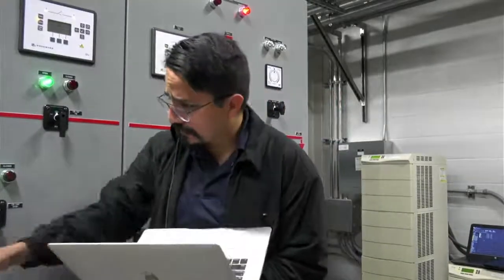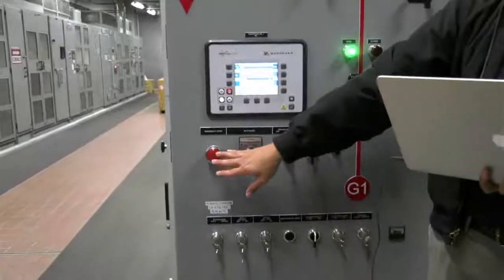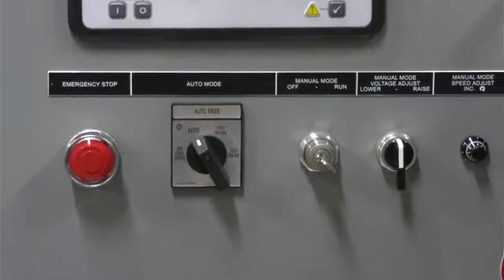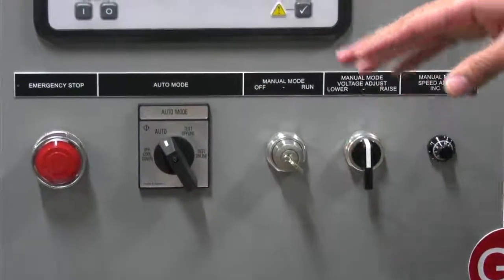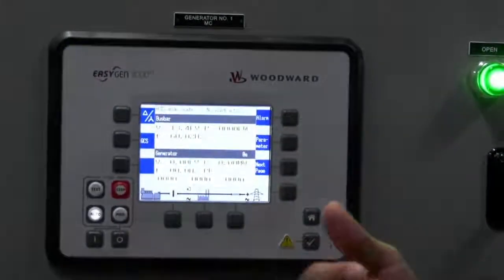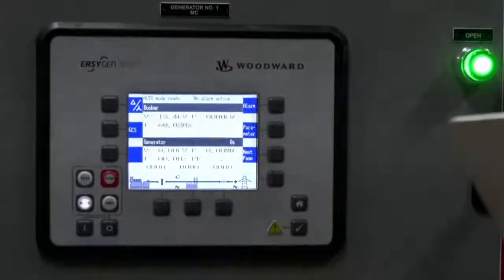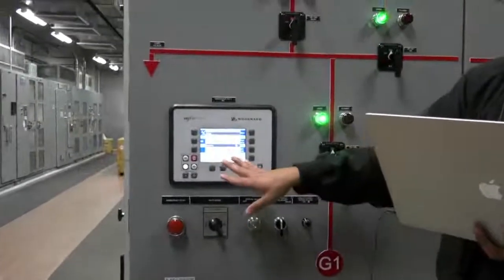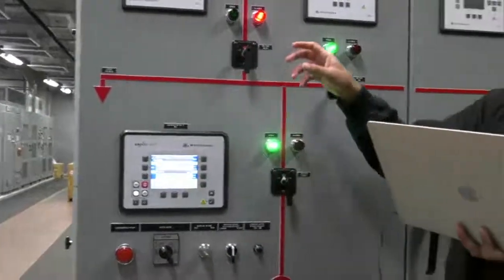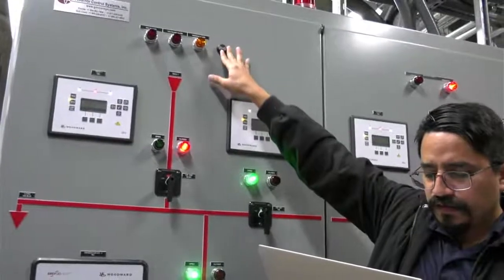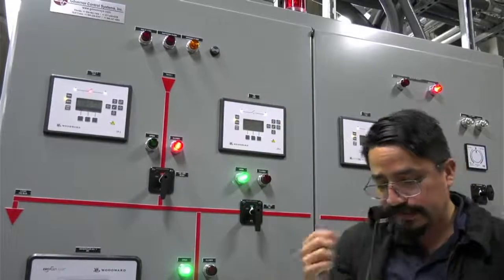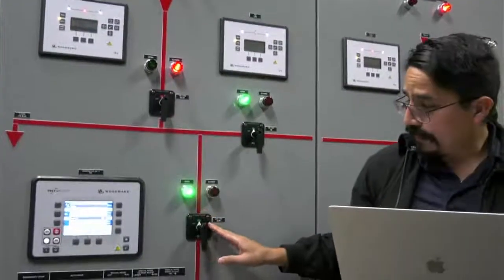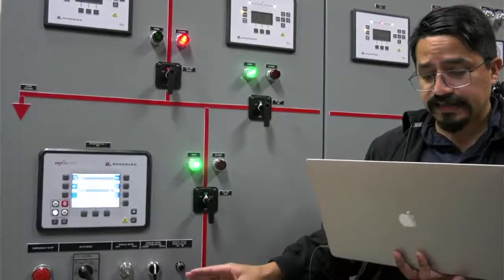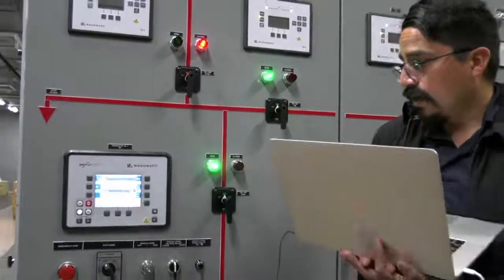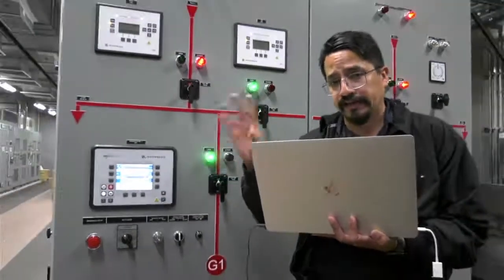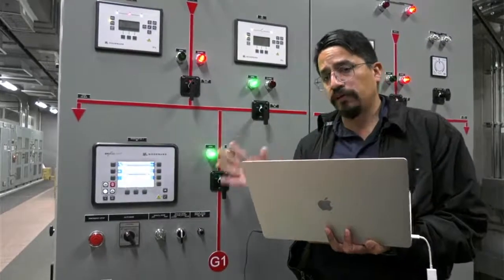On group number 5, we have this row over here. This is the emergency e-stop. What the emergency e-stop does is show an alarm here, explaining what happened and recording when the emergency e-stop was pressed. It's going to flash. Here we're going to see a flashing red. We're going to have the horn active, so there is a noise indicating there was an e-stop. It's going to open the circuit breaker, isolating the engine, and it's going to stop the engine. So basically, it's going to open and stop the engine, show alarms and activate the buzzer. It's active all the time, in manual or auto.